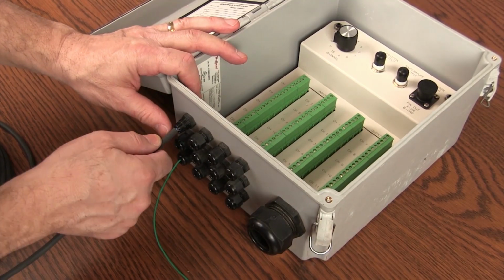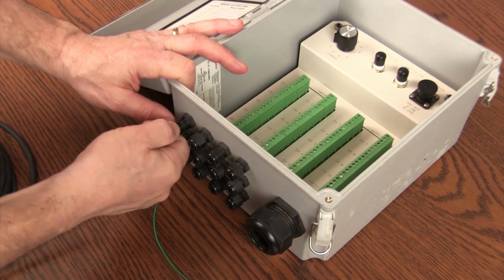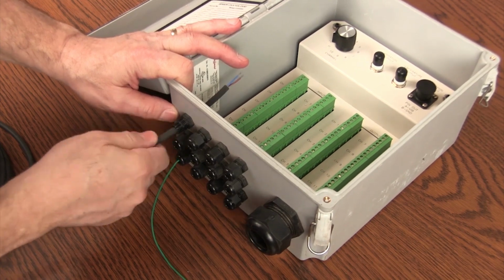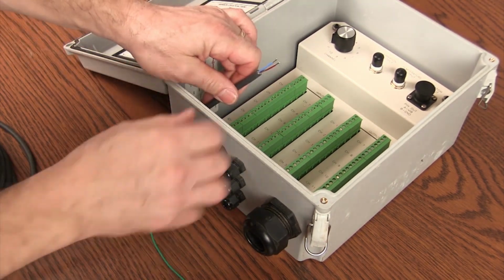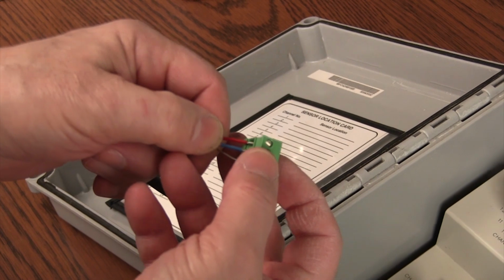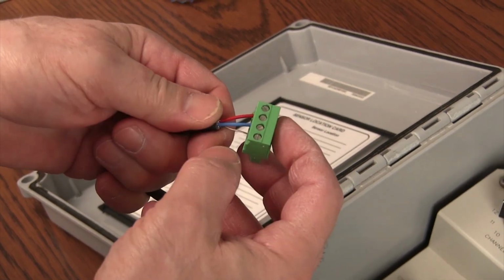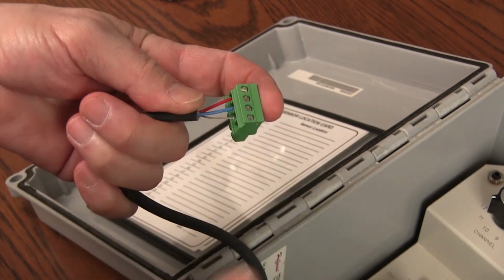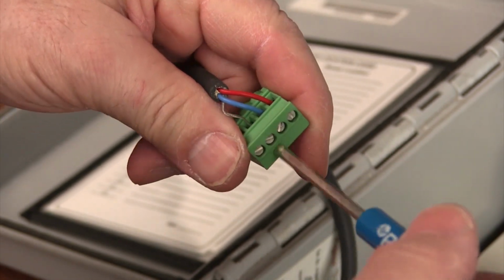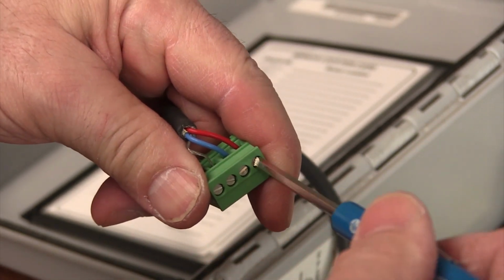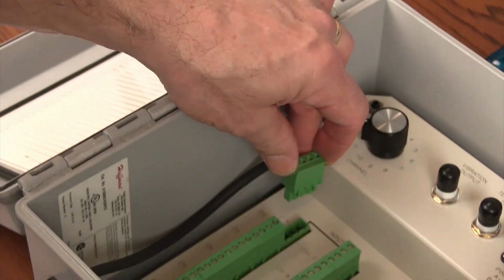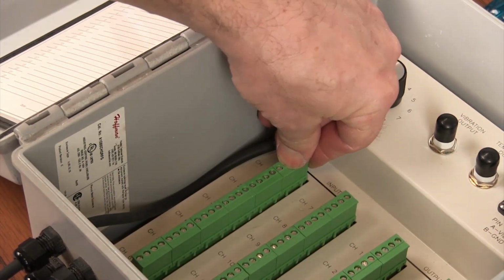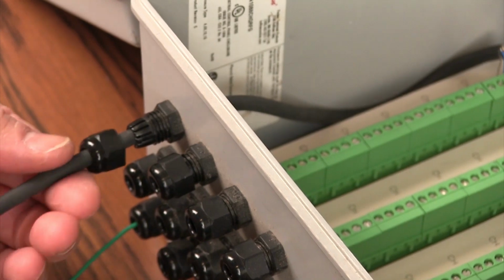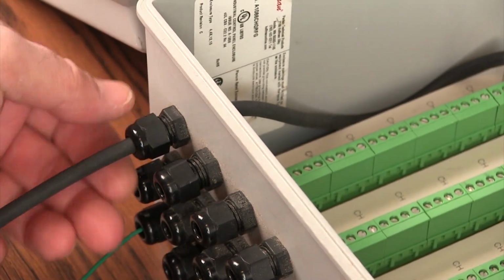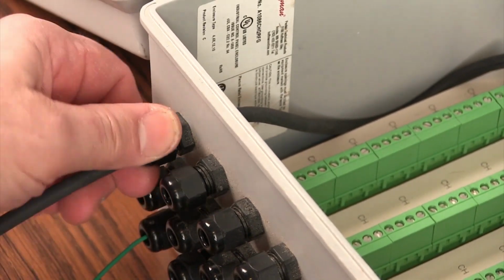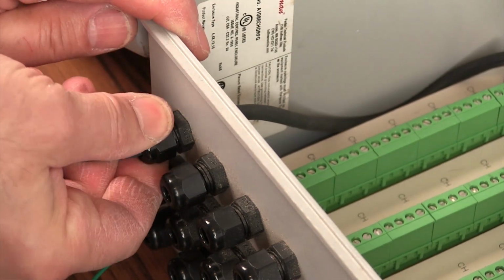The nut on the cord grip is removed and the cable for each accelerometer is fed through the bottom. For easier connection, the terminal strips on the termination box pop out. The red signal wire is connected to the positive terminal. The blue ground wire is connected to negative, and the drain wire for the shield is connected to the shield termination. Tighten the terminals with a flathead screwdriver and reconnect to the board. Once installed, be sure to tighten the nut on the back side of the cord grip. The nut acts as a strain relief for the cable and tightens a rubber O-ring around the jacket.